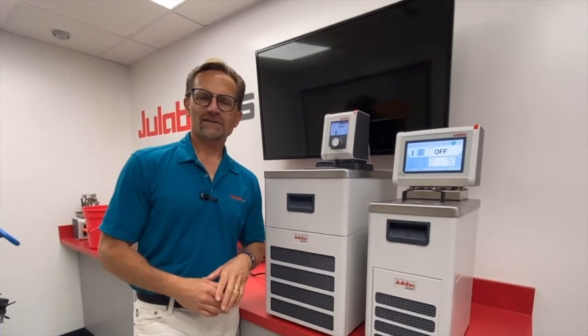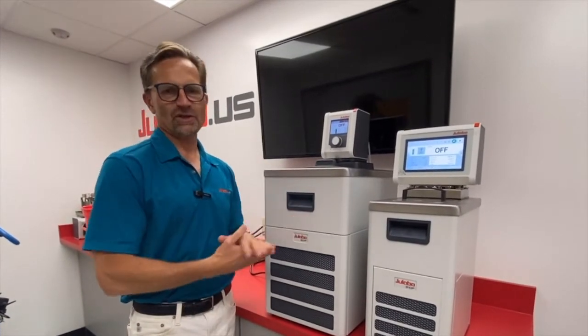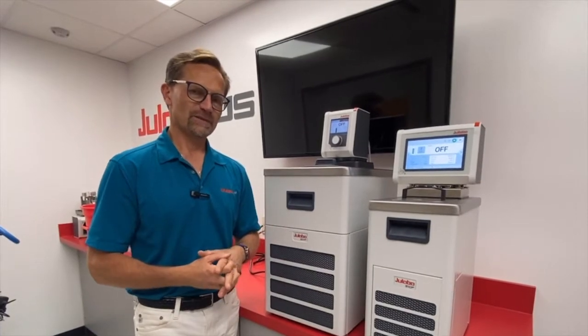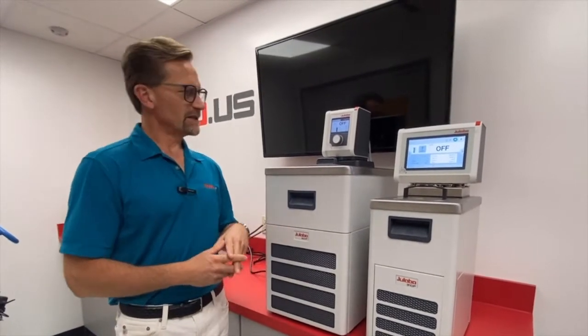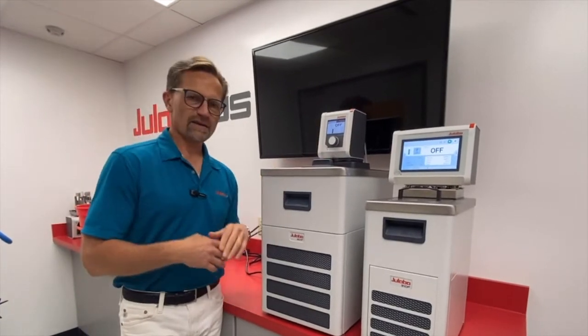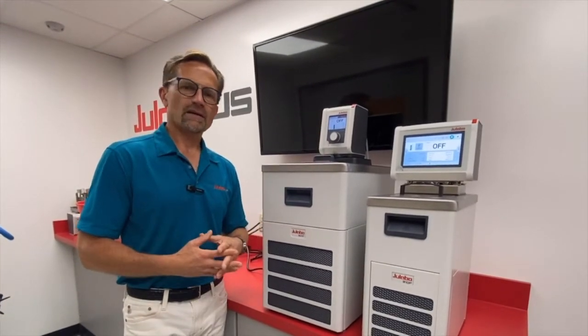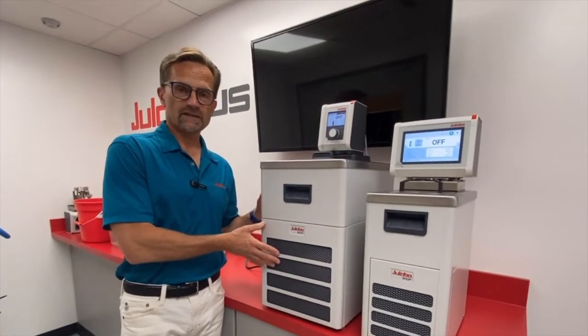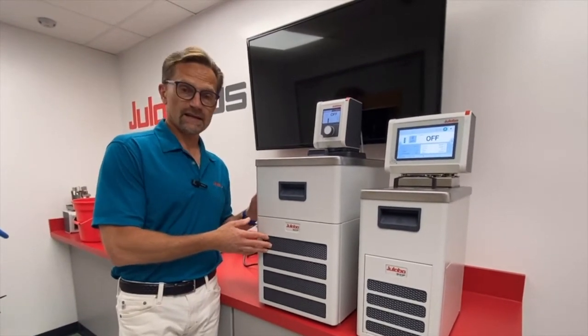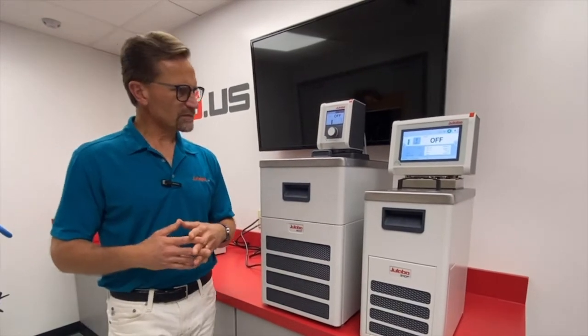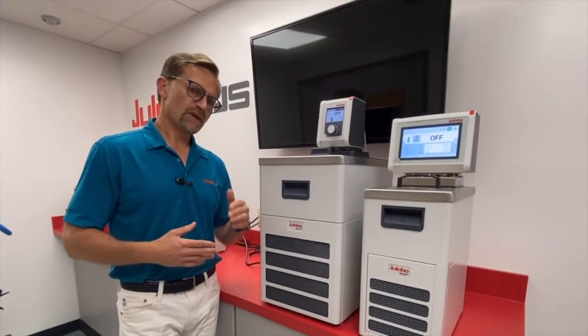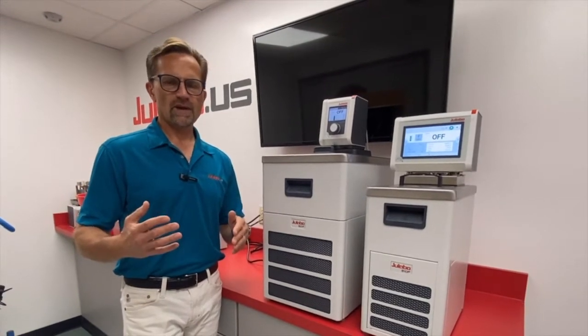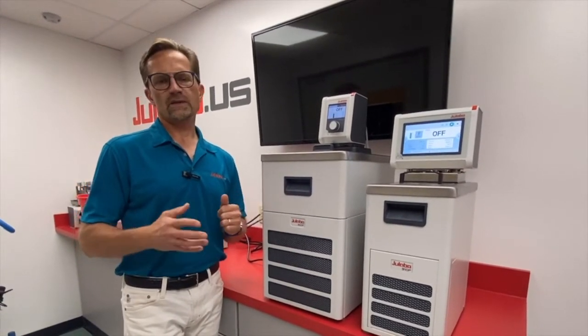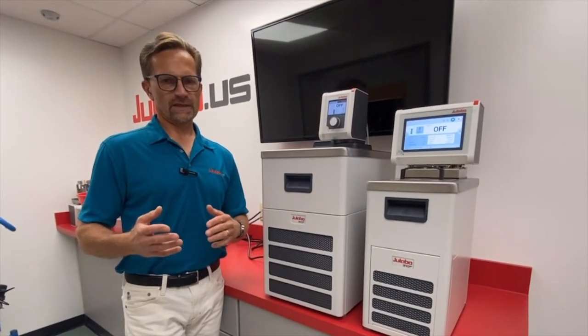And in this video I'd like to discuss the DYNEO DD and MAGIO products and how they compare to one another. So let's start with the DYNEO first. The DYNEO DD heating circulator can be optioned as a heating circulator with applications up to 200 degrees C in either 1 or 2 kilowatt heater versions. It can also be paired with refrigeration systems for refrigerated heating circulator combinations. We have 7 of those available, ranging from 200 watts of cooling power up to 1 kilowatt, with temperatures from minus 20 to 200 C down to minus 50 to 200 degrees C.